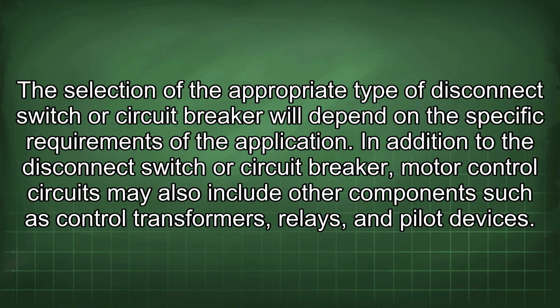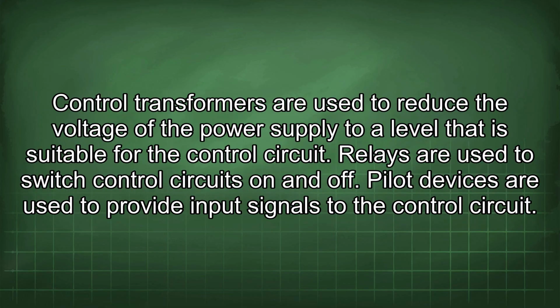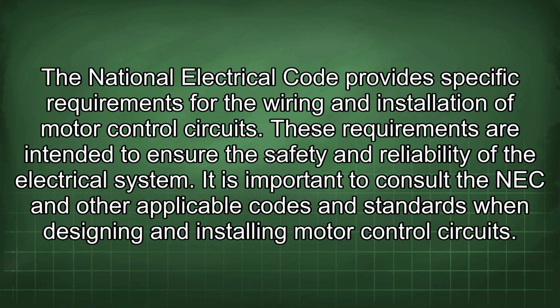requirements of the application. In addition to the disconnect switch or circuit breaker, motor control circuits may also include other components such as control transformers, relays, and pilot devices. Control transformers are used to reduce the voltage of the power supply to a level that is suitable for the control circuit. Relays are used to switch control circuits on and off. Pilot devices are used to provide input signals to the control circuit. The National Electrical Code provides specific requirements for the wiring and installation of motor control circuits.